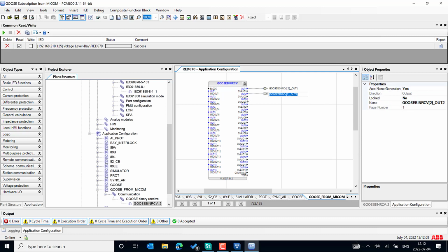And let's try to create 3 different signals, and the validity also comes below, which we can also use for getting the alert if you are using an edition 1 IED. But if you are using an edition 2 latest model IED, you are able to get the subscription monitoring with the LGOS logical node with the latest version, 2.4 and above IEDs.